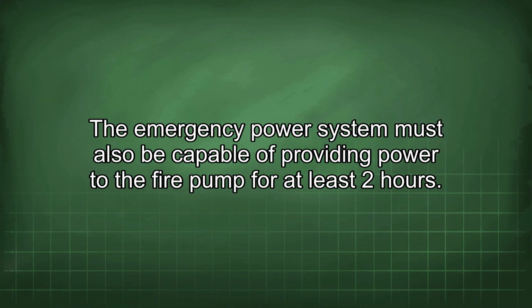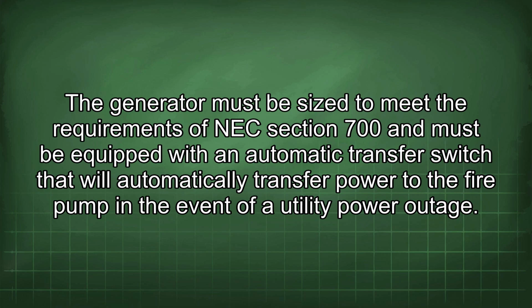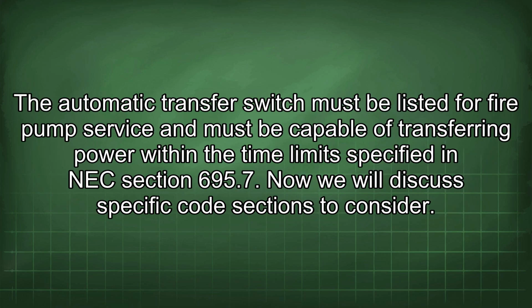The emergency power system must also be capable of providing power to the fire pump for at least 2 hours. The generator must be sized to meet the requirements of NEC section 700 and must be equipped with an automatic transfer switch that will automatically transfer power to the fire pump in the event of a utility power outage. The automatic transfer switch must be listed for fire pump service and must be capable of transferring power within the time limits specified in NEC section 695.7.